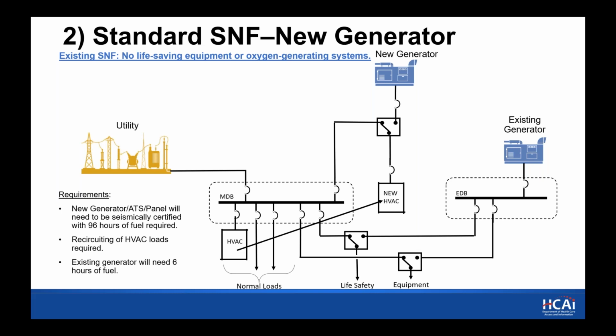All right, thank you for that clarification. Next question here, and it has to do with the MOU, but I'll ask, and it's just clarifying: can an alternate source of power, like a rented generator with an MOU in place, suffice versus a permanent generator due to real estate? So as the PIN is written, the facility will need to have 6 hours of on-site storage to run their resources for 6 hours, and then they can submit a plan of how they're going to get the remaining 90 hours to get the full 96-hour backup. And that can be done through a temporary generator.